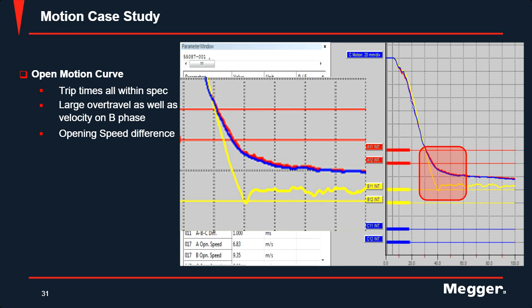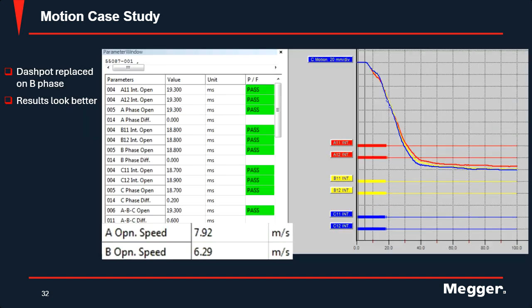But B had drastic overtravel, and the speed for B was 9.3 milliseconds versus the speed of A at 6.8. It might not sound like a lot, but when we're talking milliseconds, that's a big gap. So what they ended up doing, they figured out it was a bad dash pot on B phase. They had to open it up to verify that. They replaced it and reran the test. And as you can see, B fell in line with A and C, and our speeds came closer to each other.